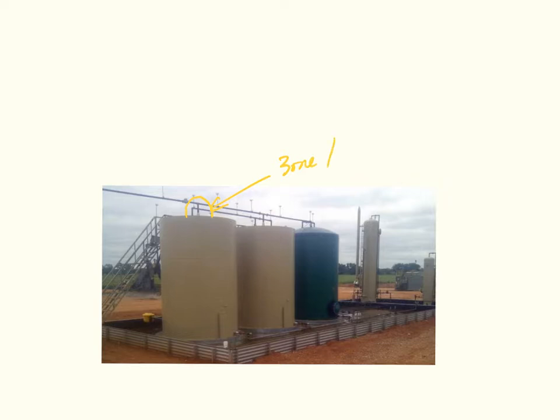That extends, of course, 1.5 meters outwards from that vent. And just to reiterate, when we're talking 1.5 meters, we're talking from the center outwards. So really, that is a radius, not a diameter.